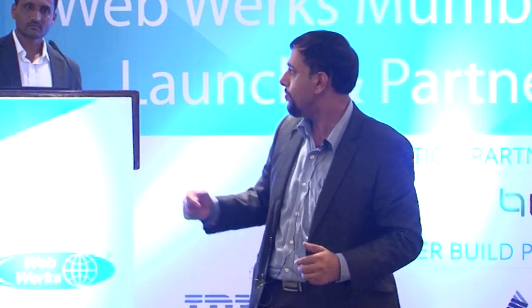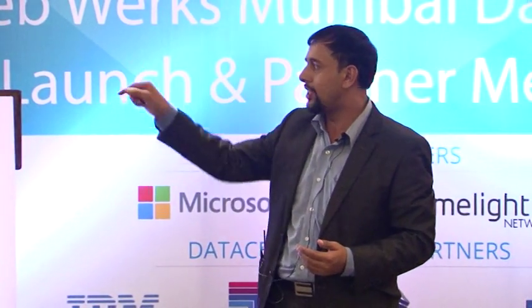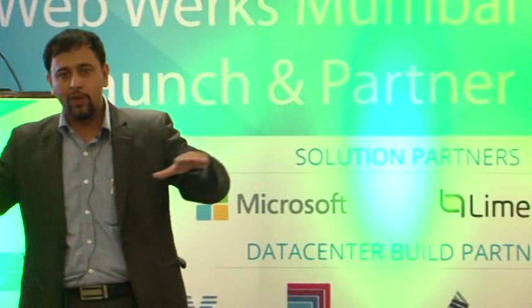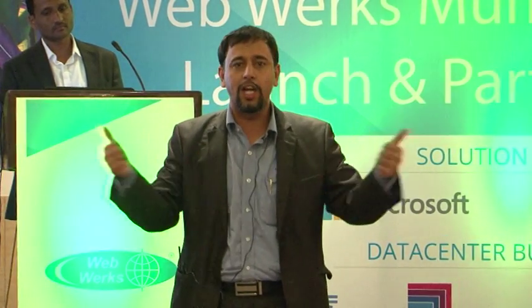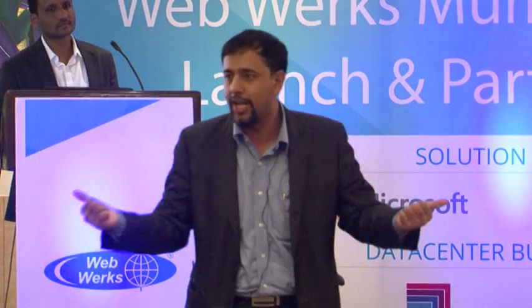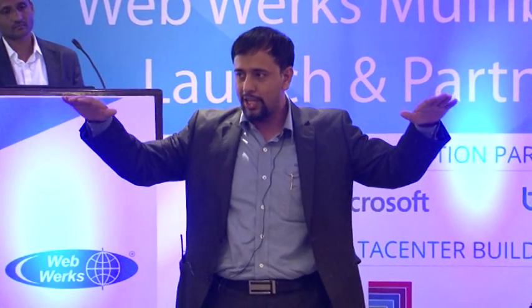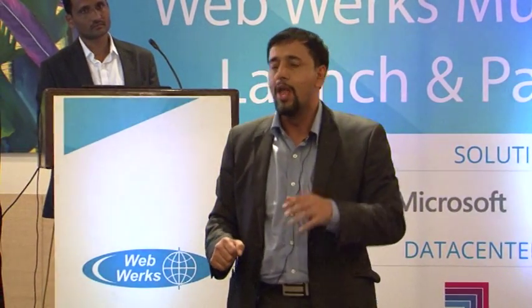With dynamic capacity control and airflow control with EC fans, we deploy cold aisle containment here at Web Werks. For this cold aisle containment, there is a unique monitoring and control method. In this data center, multiple cooling units are all connected together so they communicate — they share all alarms, set points, and failures. They share dynamic loading information, and when the load is less, all systems go down together to save maximum power.